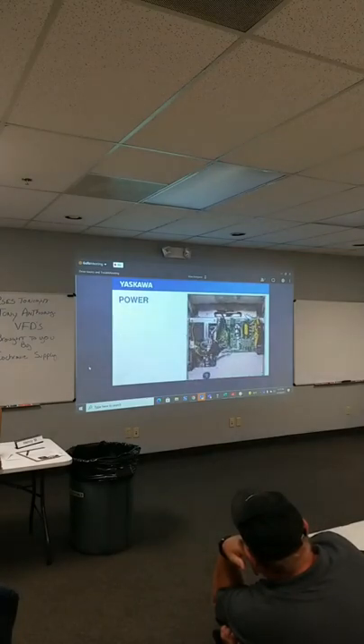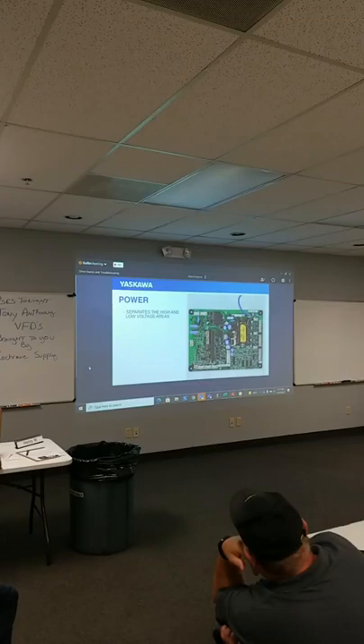Control methods available for PM, or permanent magnet, motors may also be available. This motor is similar to the induction motor we talked about before, except the rotor now incorporates magnets to create the rotor's magnetic field instead of the typical shorted rotor bars. Moving from the control side deeper into the drive, we find ourselves at the main power board. This separates the high and low voltages, converting signal levels to something the control board can read and output to. This is used for monitoring critical areas of the drive as well as controlling.